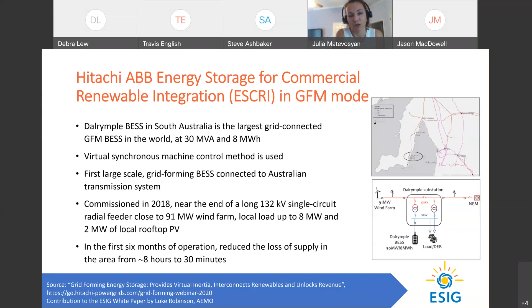All right, so this battery is designed to provide a number of functions. It can provide virtual inertial response of 2 megawatt seconds, I think is missing here, with configurable magnitude and slope. So again, here, as opposed to synchronous machine, inertia constant can be configured, and also shape of response can be configured as well if needed. This allows to reduce rate of change of frequency after sudden loss of generation and deliver that arresting power that inertia of synchronous machines is doing today. This is different from fast frequency response, as this response is nearly instantaneous. It can operate in low short circuit ratio down to less than 1.5.